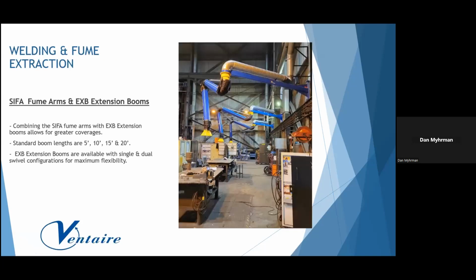What if 14 feet isn't getting the job done? We can mount these SIFA arms to an extension boom, and that's what these pictures show. Standard sizes for the booms are 5 feet, 10 feet, 15 feet, 20 feet. You don't want to get too long just because they can get cumbersome to use, and it can get to the point where they just don't use them.